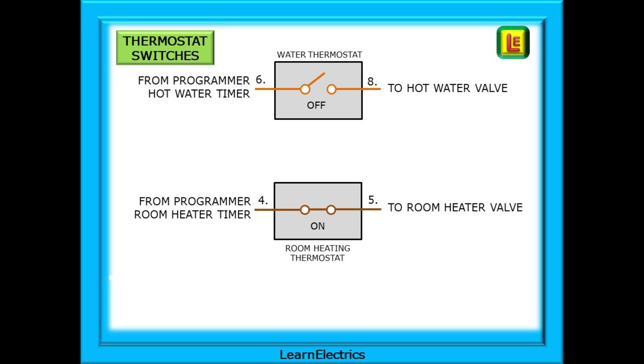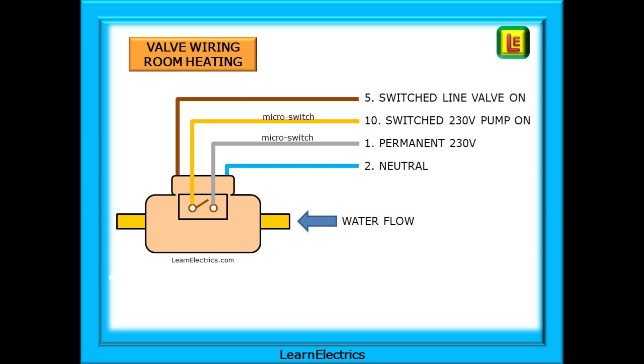Here we have shown the room heating switch is closed, in other words on and asking for heat. The output from the thermostat is connected to the switched line wire, the brown wire. There is already a permanent neutral wire at the valve. If the room heating thermostat outputs 230 volts onto the brown wire the valve will rotate and open the port for the water.